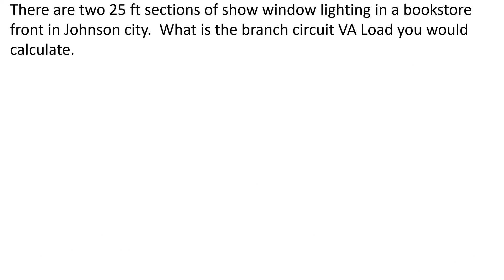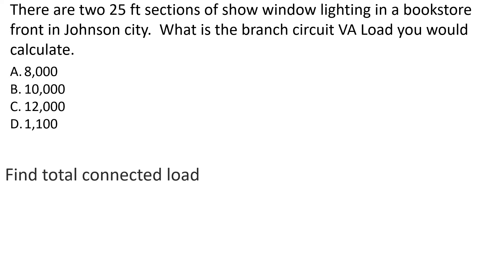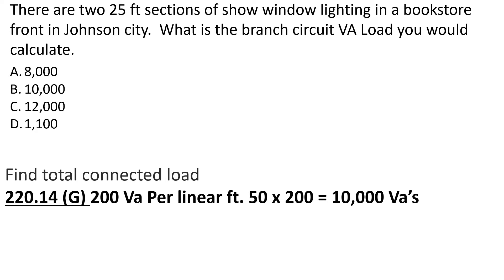There are two 25-foot sections of show window lighting in a bookstore front in Johnson City. What is the branch circuit VA load that you would calculate? Step one: find our total connected load. We're going to head to 220.14G, which lets us know that it's 200 VA per linear foot. We take our 50 feet multiplied by 200 VAs each, giving us a starting connected load of 10,000 VAs.